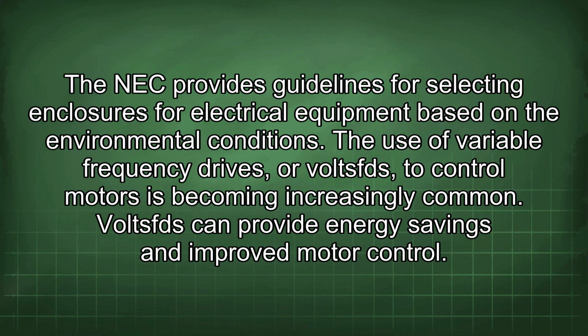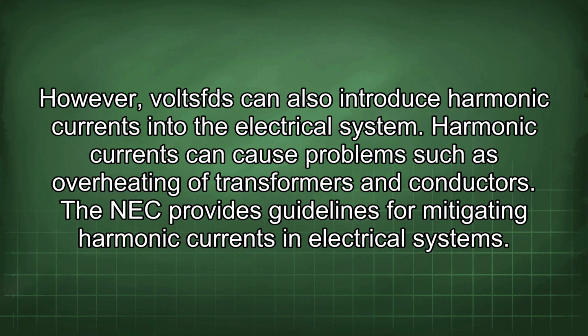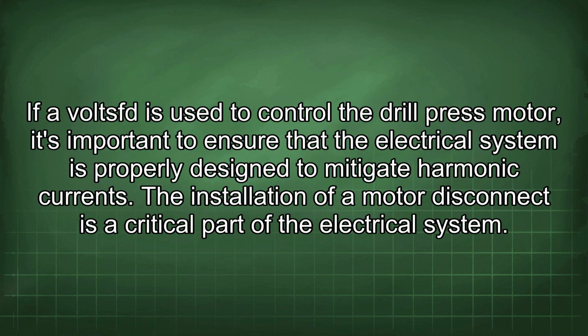The use of variable frequency drives, or VFDs, to control motors is becoming increasingly common. VFDs can provide energy savings and improve motor control. However, VFDs can also introduce harmonic currents into the electrical system. Harmonic currents can cause problems such as overheating of transformers and conductors. The NEC provides guidelines for mitigating harmonic currents in electrical systems. If a VFD is used to control the drill press motor, it's important to ensure that the electrical system is properly designed to mitigate harmonic currents.